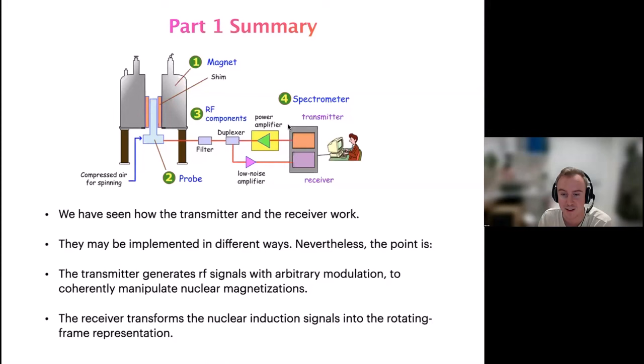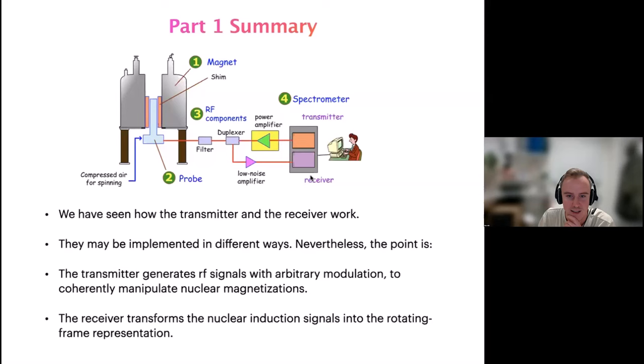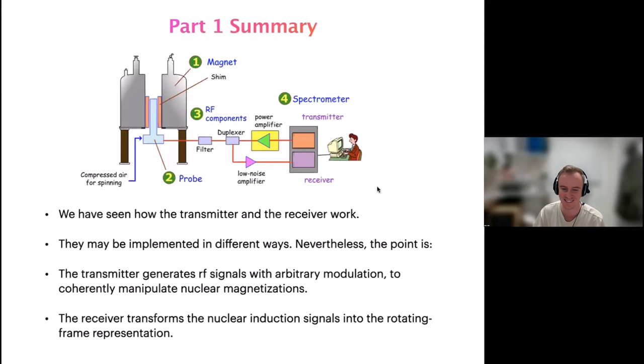There are still more slides — let me continue. One more question: from Aksa Gansmada, is it possible to run NQR experiments below 6 MHz? Yes, we do, even though there is often a lot of RF interference at those frequencies. Let's pause questions here and continue with Part 2.